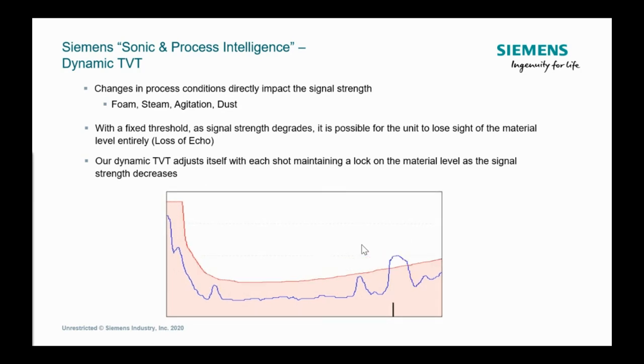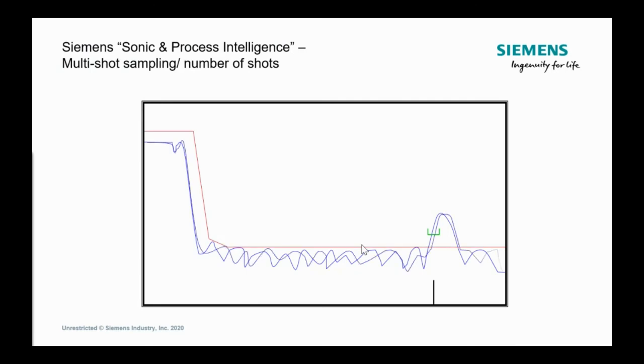So that's something that is key or different in the Siemens instruments, is the fact that that signal reference line, or our TVT, or time varying threshold, is calculated each and every time. Okay. Something else that we do is called multi-shot or sampling. And this kind of happens behind the hood. So what it does is it will take a whole number of measurements. That number of measurements typically by factory default is about 20.